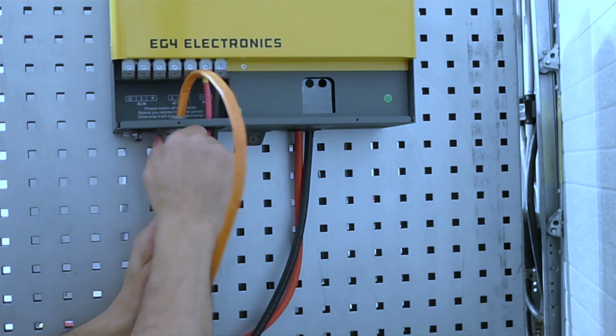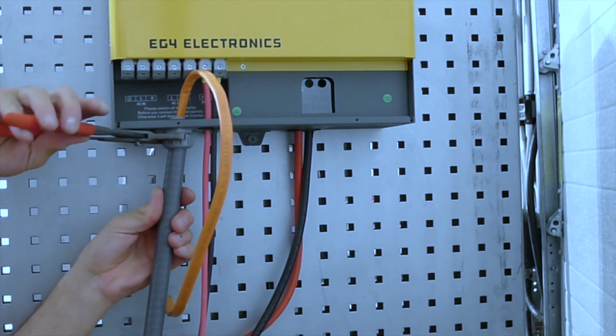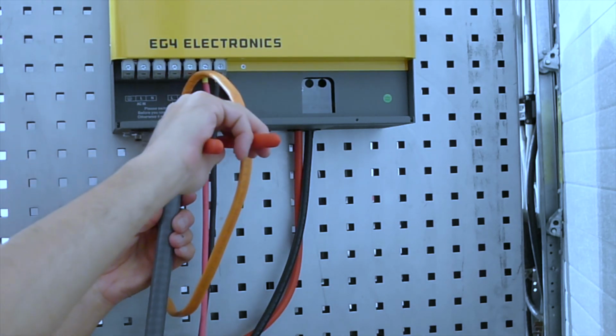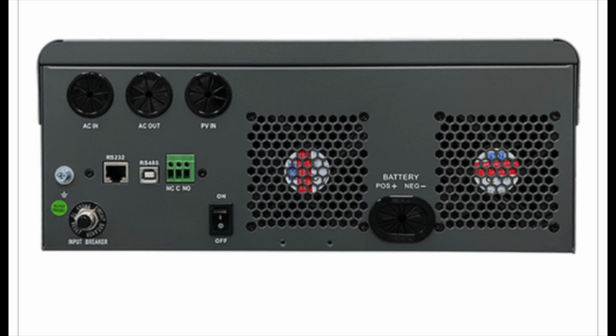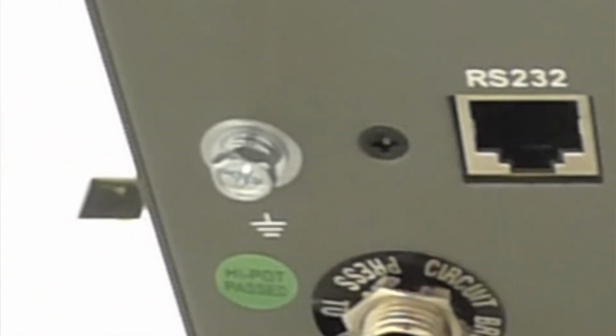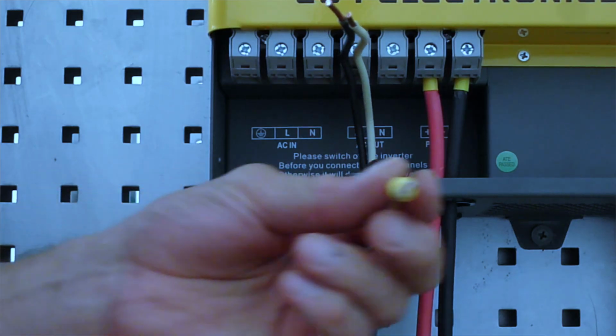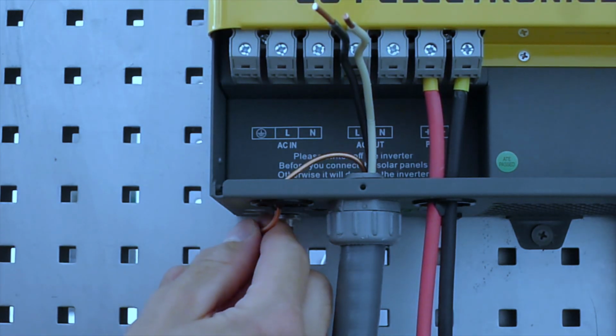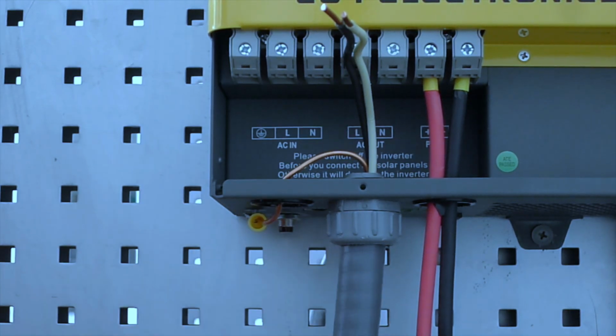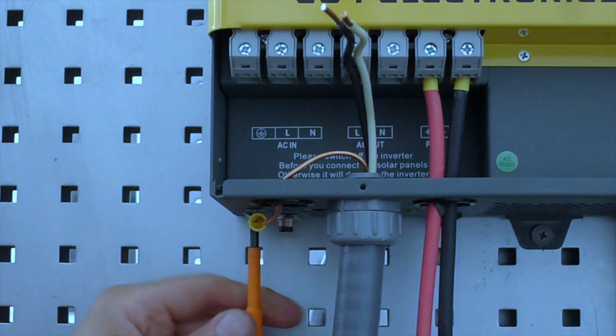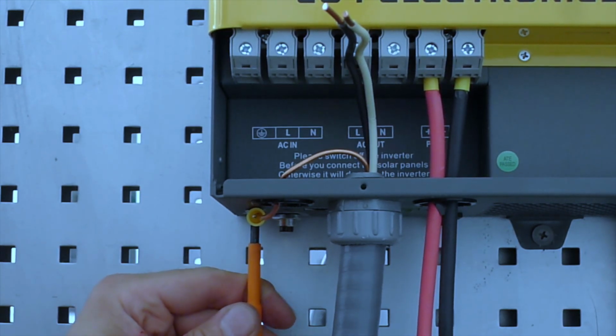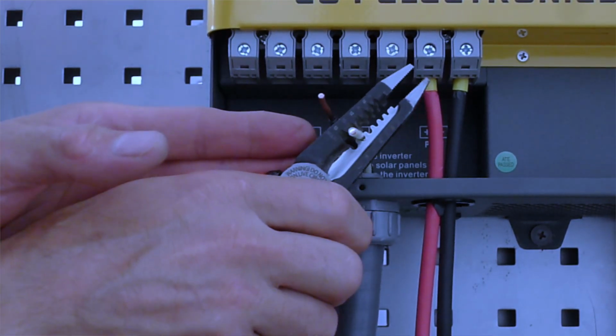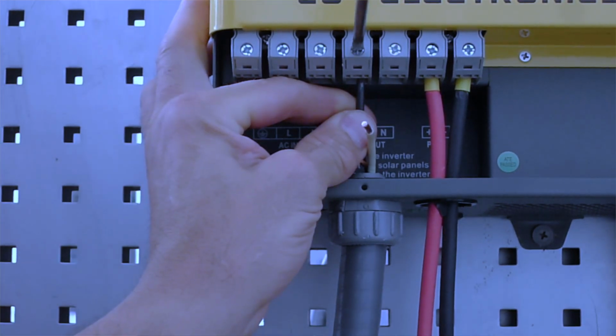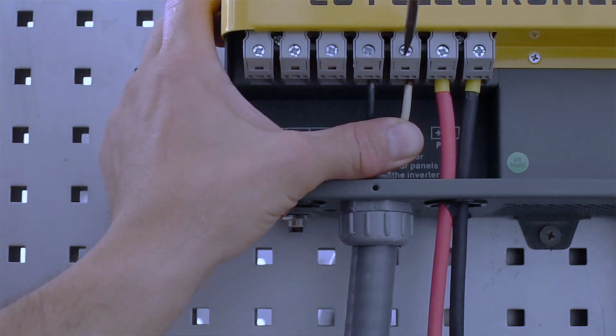Now let's use a 10 gauge wire for AC out. Unfortunately, the ground connection point is designed outside of the service panel, so we are going to bring it in and out at the next service hole. We also have to crimp a wire connector to be able to attach it with a bolt. We are going to remove the insulation sleeve for the same length, 10 mm or 0.4 inches, at this location, and we are connecting the black wire to load and the white wire to the neutral terminal.